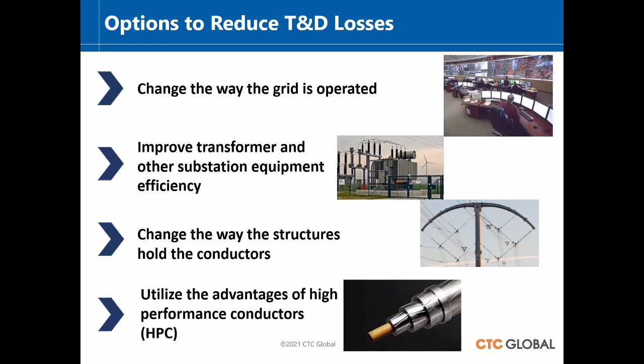And finally, I list high performance conductors or high efficiency conductors. In Minnesota, they looked at the way the grid is operated, transformer changes, and high performance conductors. They did a study over about 20 to 30 years and found a 30% reduction in line losses. About 25% was due to changes in operating the grid during peak periods, about 25% was transformer improvements, but the surprise was half of that benefit came from utilizing advanced high performance, high efficiency conductors.